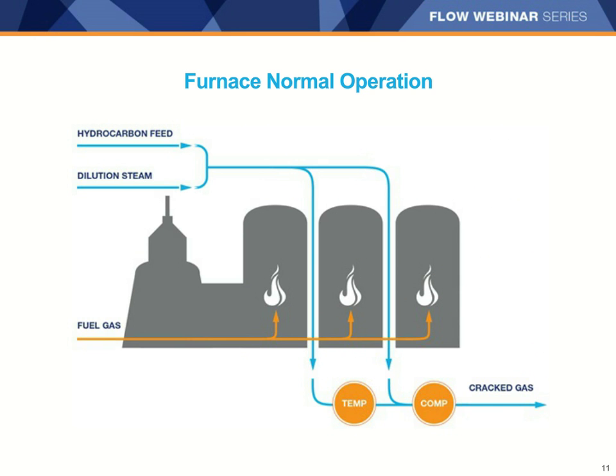There are essentially four process streams in the furnace section during normal operation. Those are the three feeds: fuel gas for combustion mixed with air, the hydrocarbon feed which is typically naphtha or ethane, and the dilution steam. There is also cracked gas coming out of the furnace. There are two primary variables controlled for optimization: the temperature of the cracked gas, typically called the coil outlet temperature or COT, and the composition of the cracked gas. During normal operation, the goal is to optimize the yield to produce the highest value of products and to minimize the coking rate.